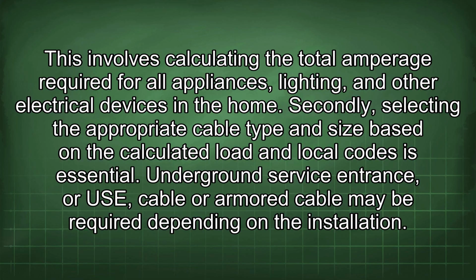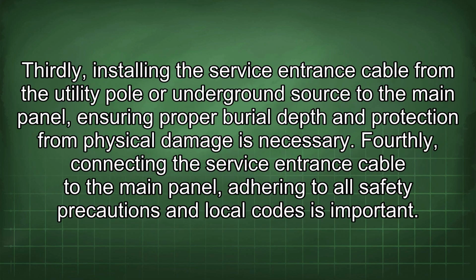Secondly, selecting the appropriate cable type and size based on the calculated load and local codes is essential. Underground service entrance or USE cable or armored cable may be required depending on the installation. Thirdly, installing the service entrance cable from the utility pole or underground source to the main panel, ensuring proper burial depth and protection from physical damage, is necessary.